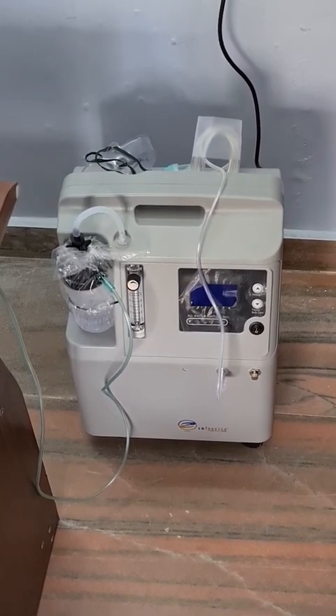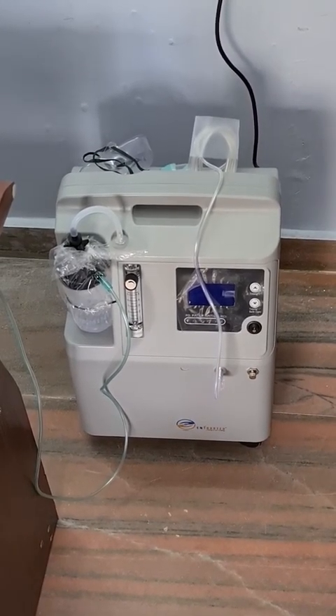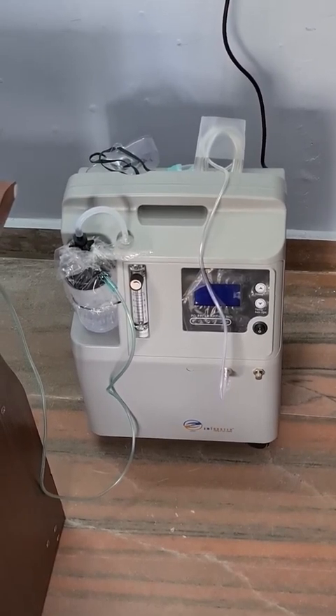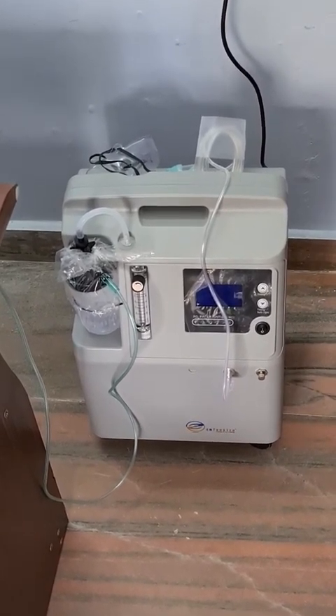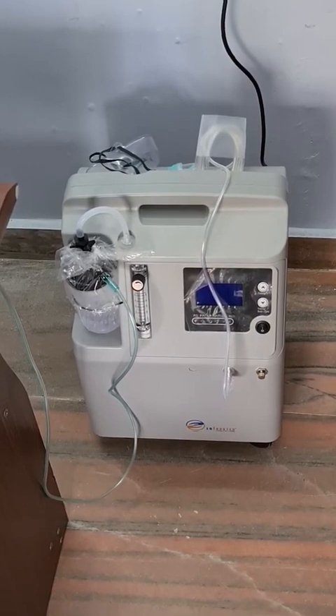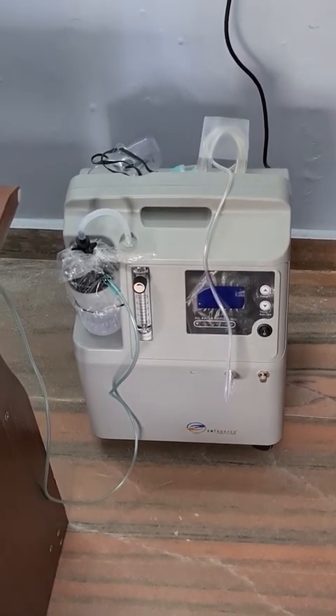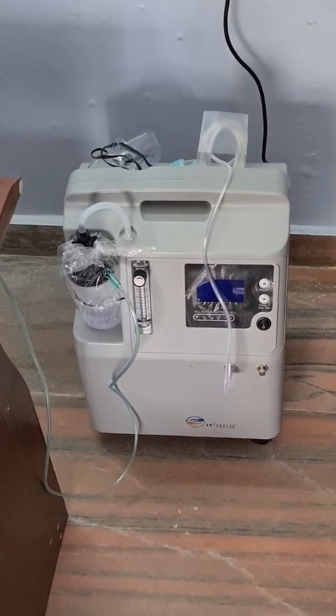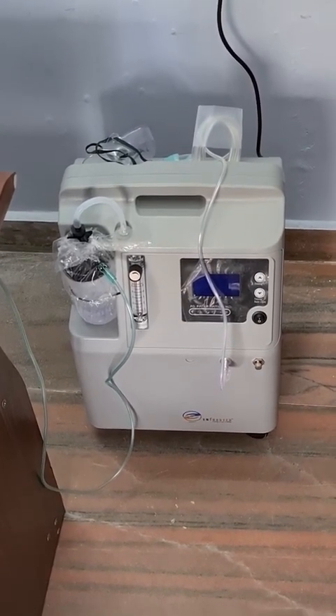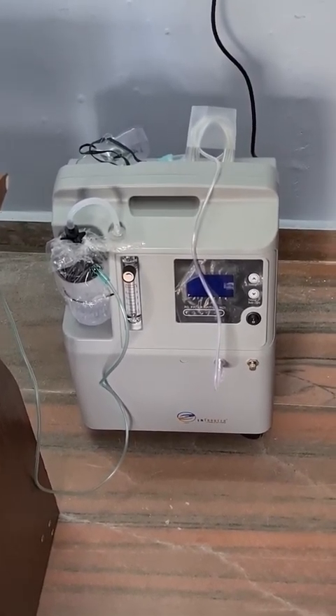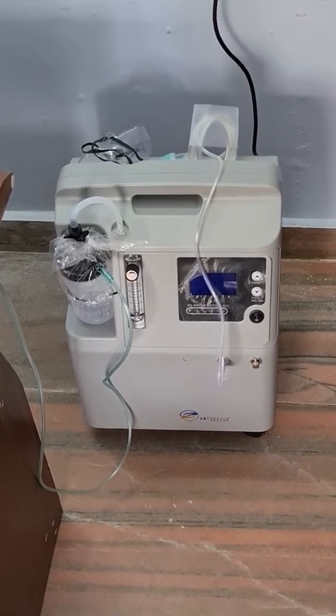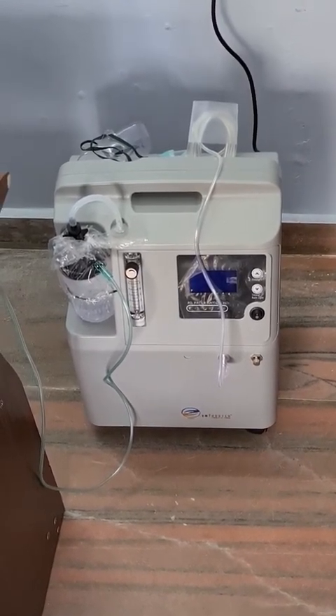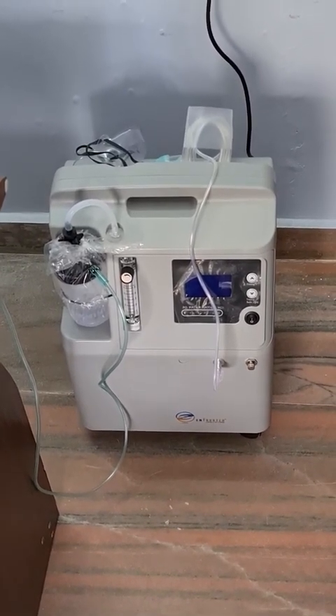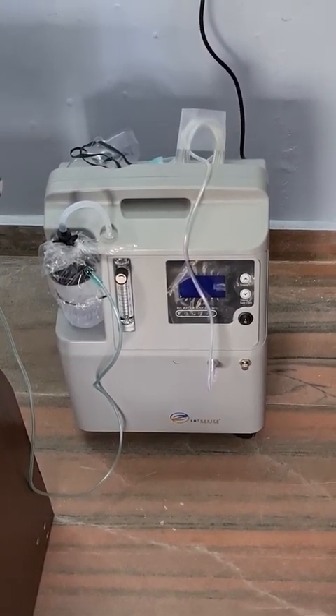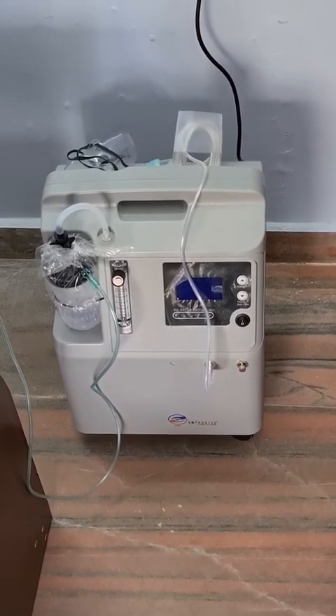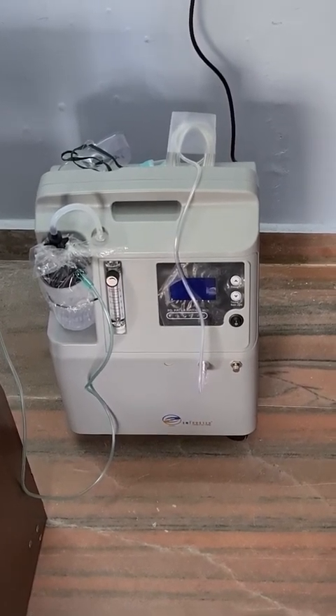If you get any stabilizer which is not exactly compatible with oxygen concentrators, you are still going to get the same error. Whenever the voltage is fluctuating, you may get the low pressure or high pressure alarms. Whenever you get that alarm, the machine will go into a fail-safe mode. The machine is not going to get damaged, but at the same time you will not get the oxygen output. It will go into a standby mode, and until it gets back the proper voltage, the machine will not switch on. So the main thing about the concentrator is proper voltage.